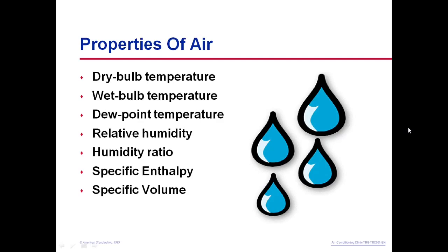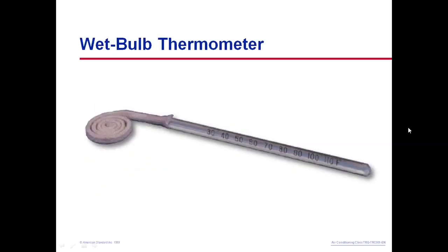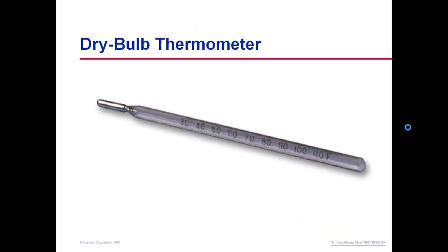These are seven properties found on the psychrometric chart. If we know any two of these seven properties, we can locate the condition of air on the psychrometric chart, and the other five properties can be read from it. The three temperatures are dry bulb, wet bulb, and dew point, along with relative humidity, humidity ratio, specific enthalpy, and specific volume.